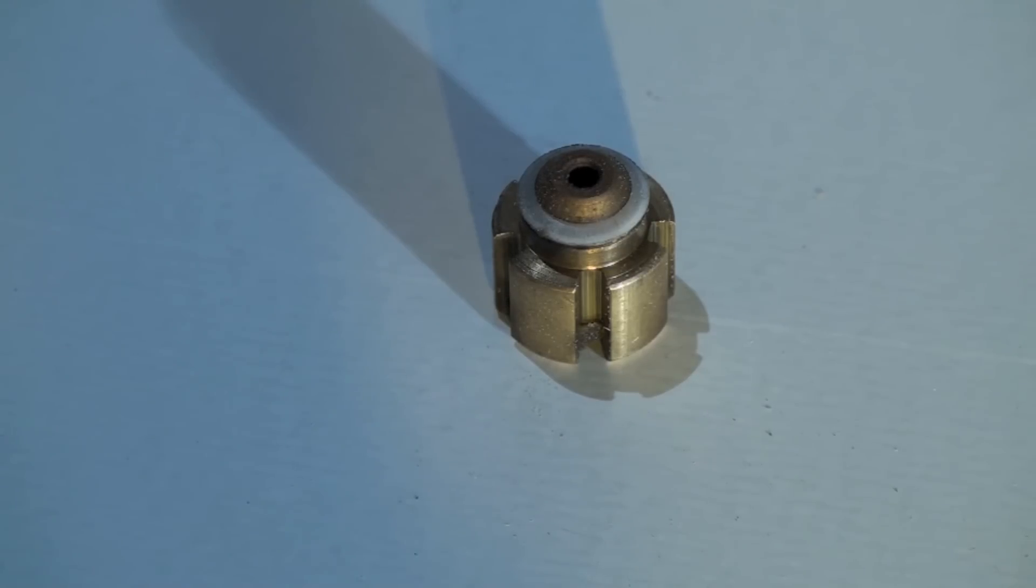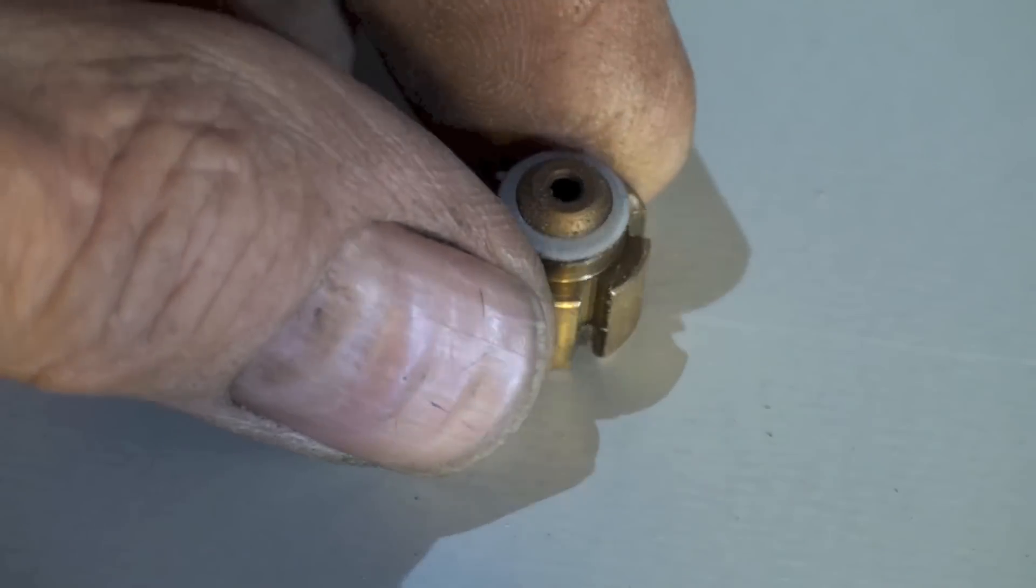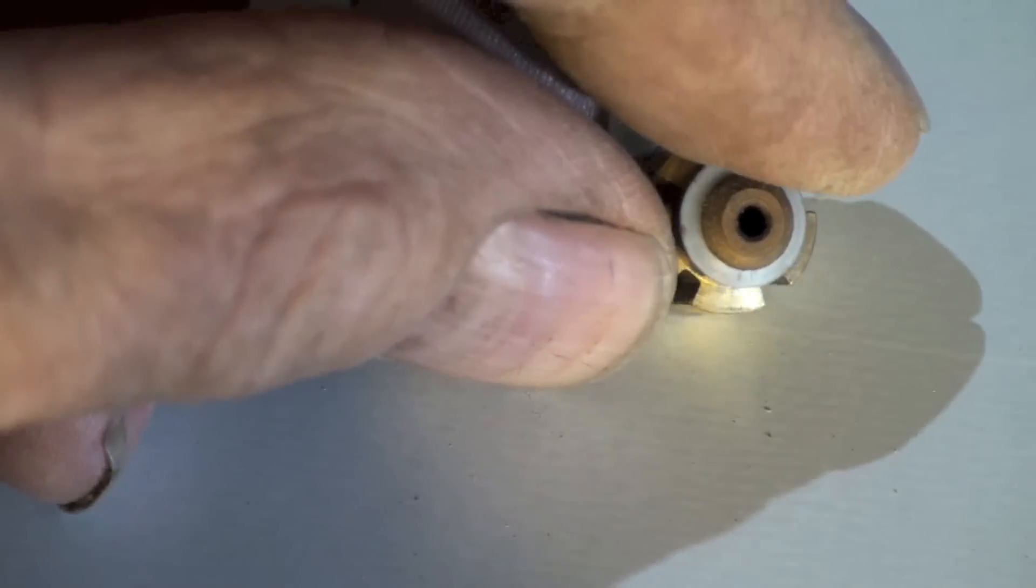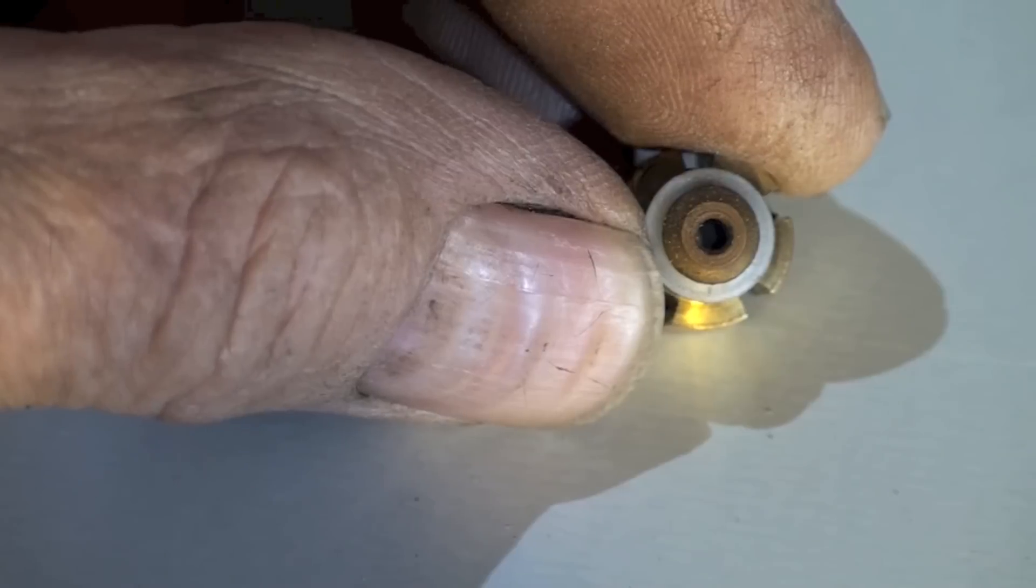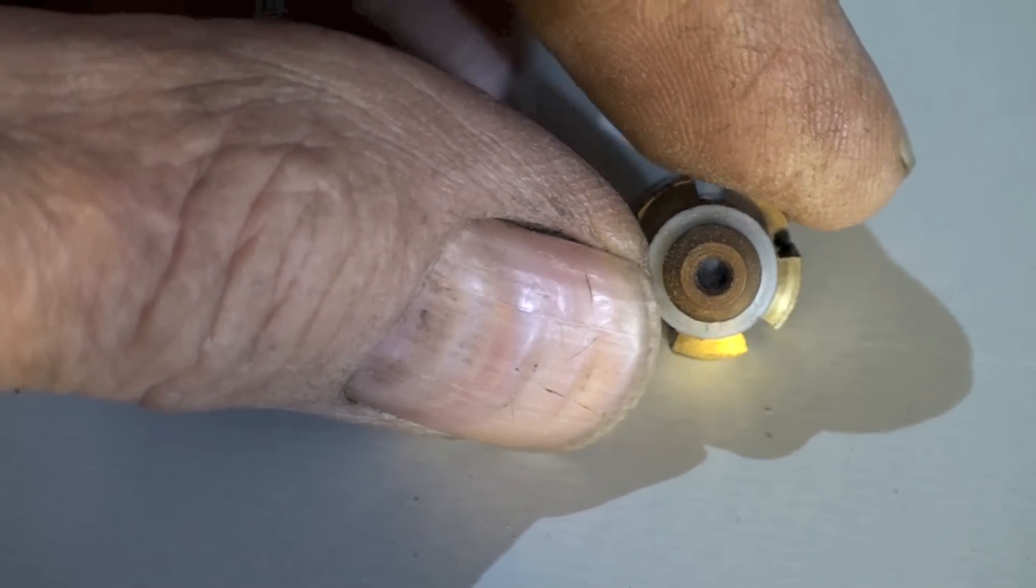If it's a heat pump, in the summertime the indoor coil's an evaporator, so you want it to go through this. This little gasket is going to hit up against a surface inside that body and only allow the refrigerant to go through that hole.